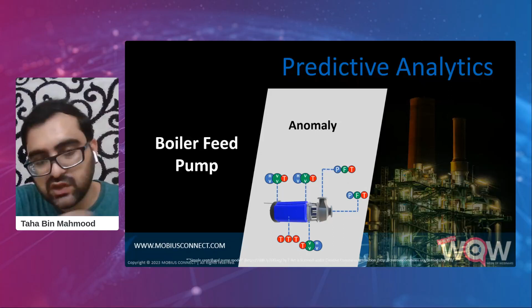So what actually happened was that this was the pump, which has certain instrumentation installed with it. When seen in a global view of the system, we see that this particular pump had a lube oil system associated with it as an auxiliary system, which had an associated heat exchanger, supplied with cooling water by a dedicated cooling water system as well, right? So what actually happened was that a temperature rise of 5 degrees was observed at the motor non-drive end, well below the customer alarm limits.